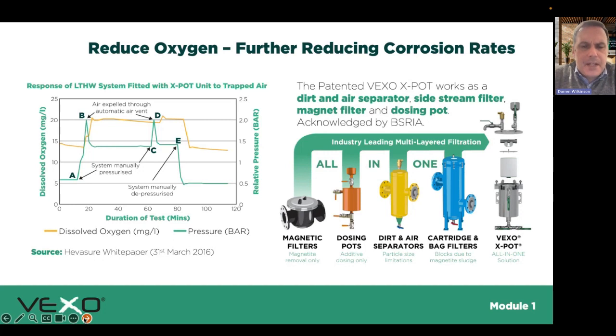Heating systems, if I'm honest, you probably find a lot of that oxygen has been used up with the temperature in any case by the time the degasser is looking to do any work. But I certainly see the benefits on chill water systems in particular, and cooling water systems, highly valuable I would say, because the other way that we remove dissolved gases is through temperature. As I said, if temperature increases, they naturally want to come out, and they'll come into that free air state, and they'll come out of an automatic air vent. So there is a correlation. If you remove more of the free air, you will pull out some, not all, but some of the dissolved oxygen as well.